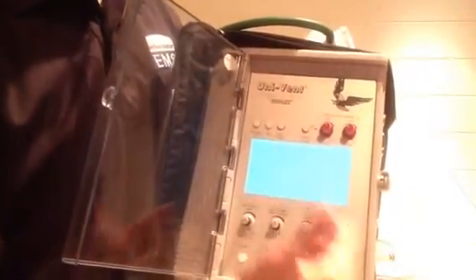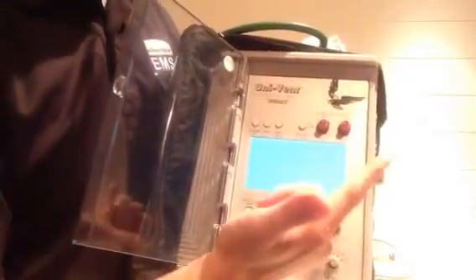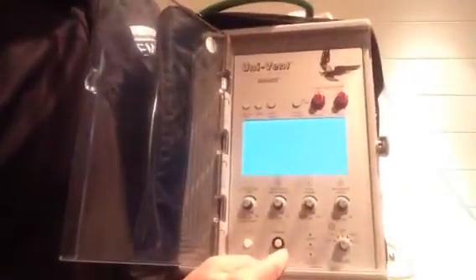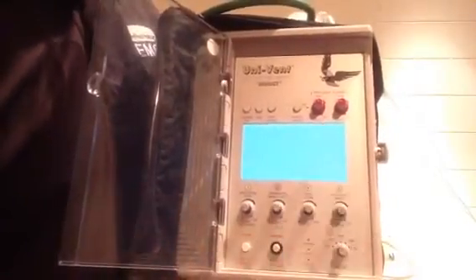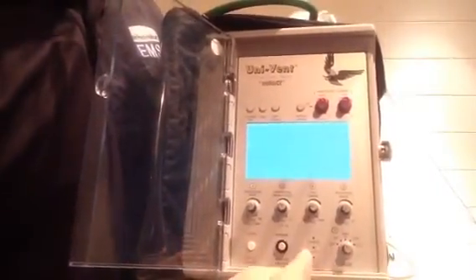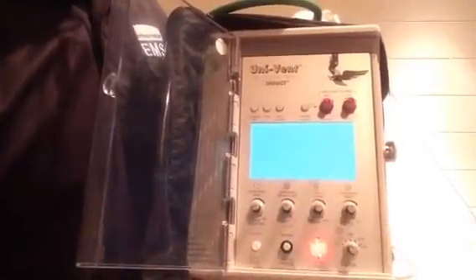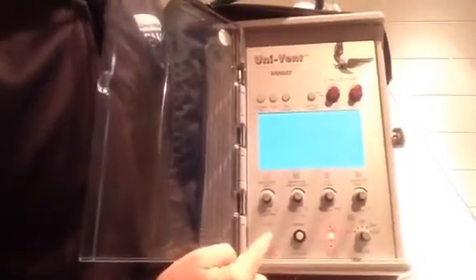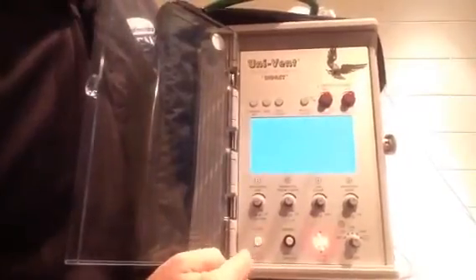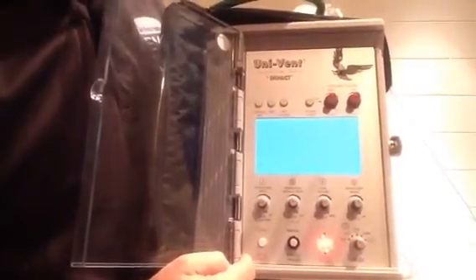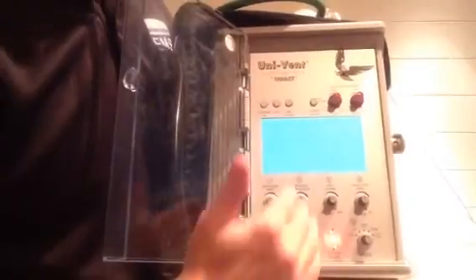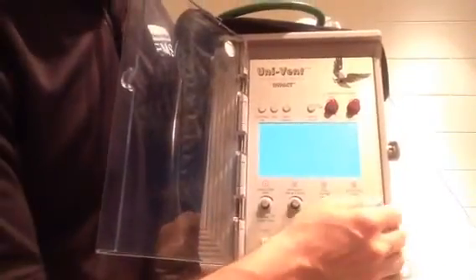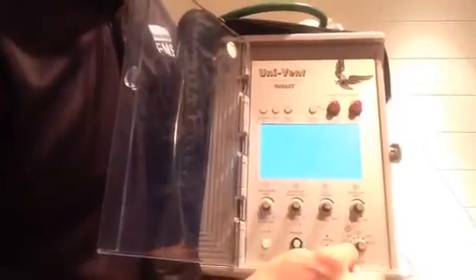And it's alarming because the 50 psi line is not currently hooked up to an oxygen source, and it can sense that. That's kind of a nice feature, because if you were to run out of oxygen or forget to hook it up to oxygen, it's alarming you, telling you that there's something wrong. So once we solve the issue, the alarm automatically goes off. But if we had the issue and the alarm's going off, we can hit the alarm silence button right here. And it's just going to mute it for a little while. It'll eventually come back on because we don't want alarms to ever be fully muted. So we'll turn that off for right now.